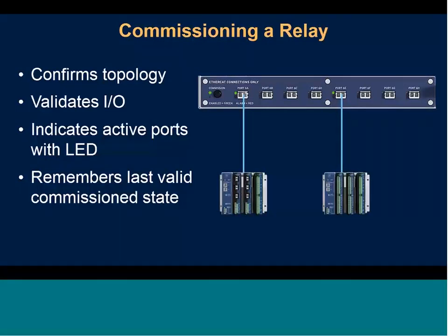But the idea with this is I can test a relay and Axions on, let's say, a test bench. I can have them associated, and then when I move it to the actual field installation, the relay will remember how it was commissioned, and as long as I connect everything exactly like I did at my test bench in a controlled environment, the relay will just enable. If I miss any of my connections, then the relay has ways of signaling that with the LEDs. So we can know which port is the problem, and we know that the problem has to be between that connection on the relay and the connection on the Axion.